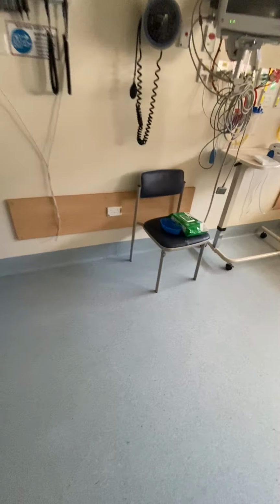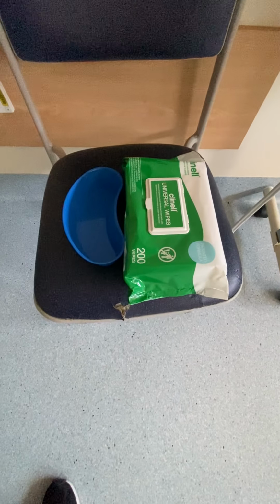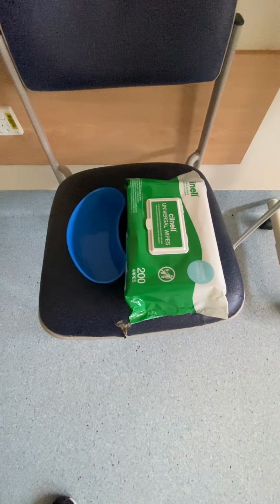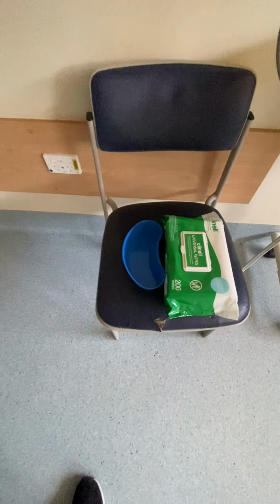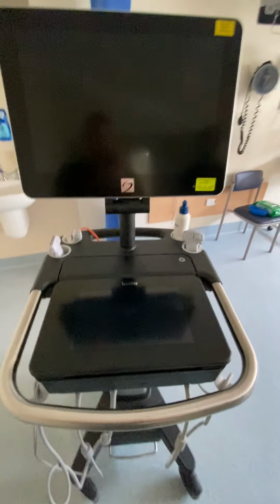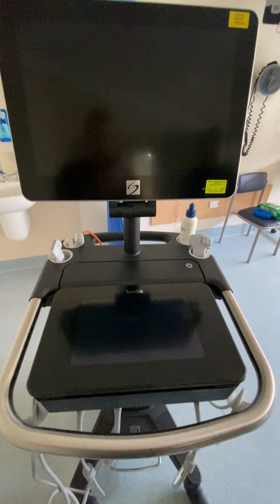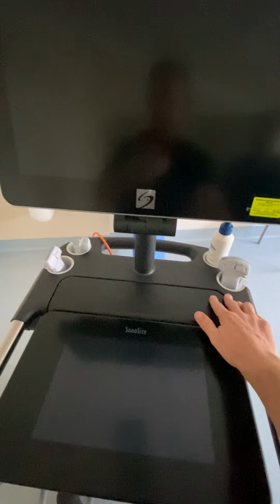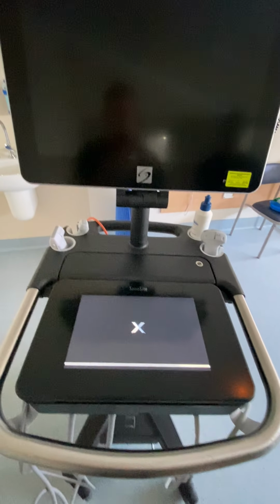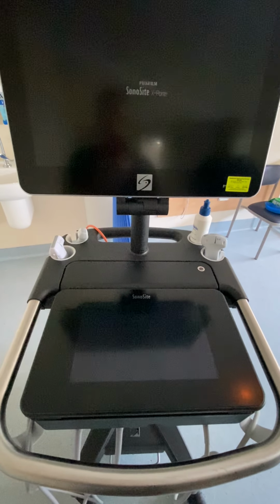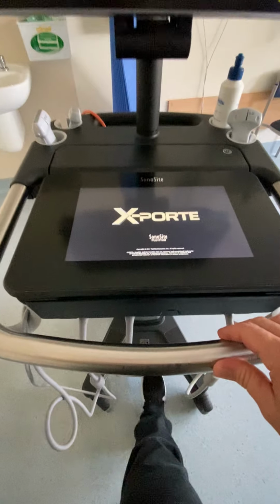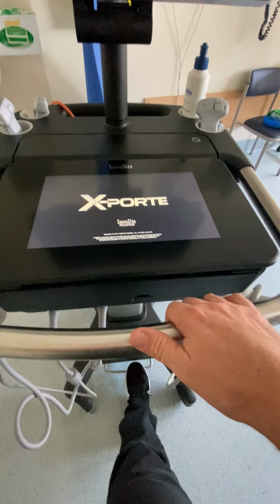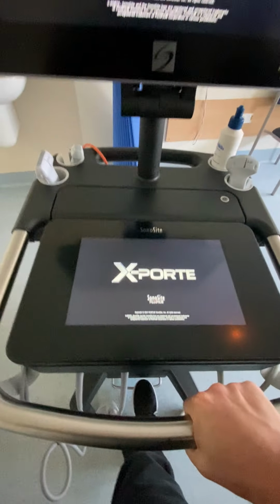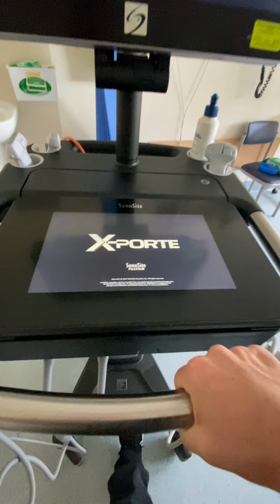Pre-using the machine, we'd recommend a wipe down with Clinell wipes, detergent wipes, to clean the transducers, cables and the machine itself. They're non-damaging to the machine and are much more effective and safer than alcohol swabs. To turn on the machine, there's a power button at the side. It typically will turn on relatively rapidly. To adjust machine height, you can press on the foot pedal on the bottom, which will allow you to move the machine downwards or upwards to a comfortable height.